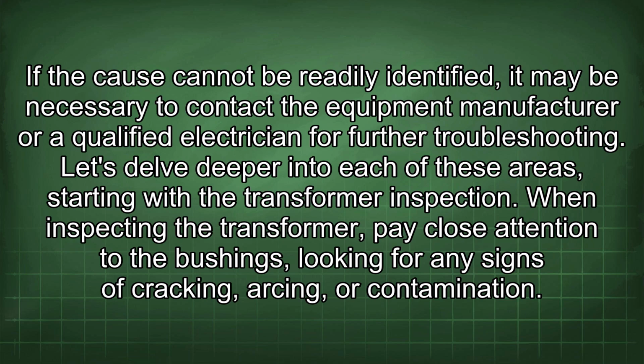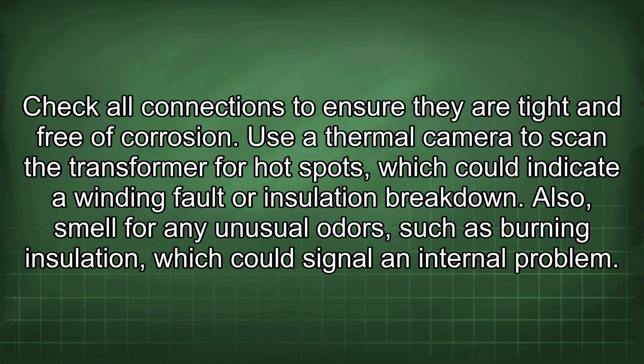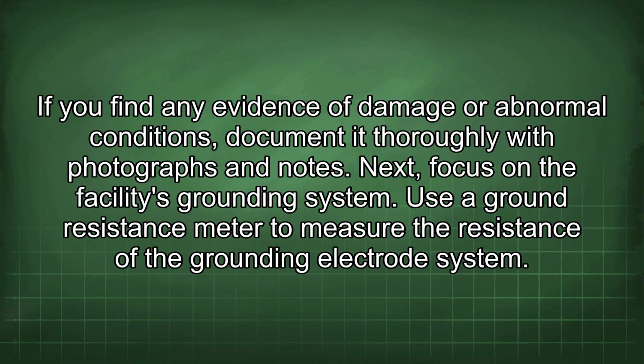When inspecting the transformer, pay close attention to the bushings, looking for any signs of cracking, arcing, or contamination. Check all connections to ensure they are tight and free of corrosion. Use a thermal camera to scan the transformer for hot spots, which could indicate a winding fault or insulation breakdown. Also, smell for any unusual odors, such as burning insulation, which could signal an internal problem. If you find any evidence of damage or abnormal conditions, document it thoroughly with photographs and notes.